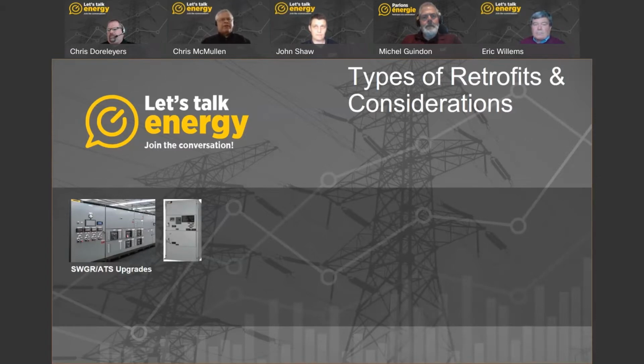Breaker upgrades are another example we have, using old enclosures and bus bars, electrically operated, or advancement in fault monitoring at the breaker. We could tie this topic to new updated protective relays with up-to-date coordination studies, maybe because of changes in the facility or expansion. One example of this is a substation with updated breakers for use with the new generator for closed transition. Breaker speed is critical, and the older breakers just weren't up to the task.